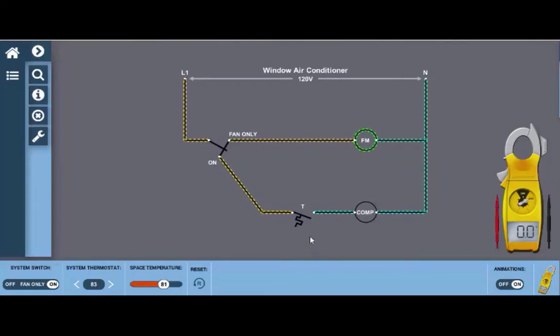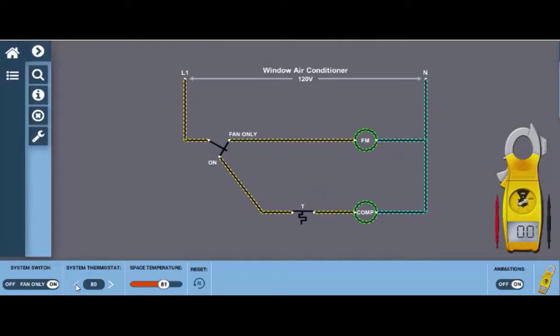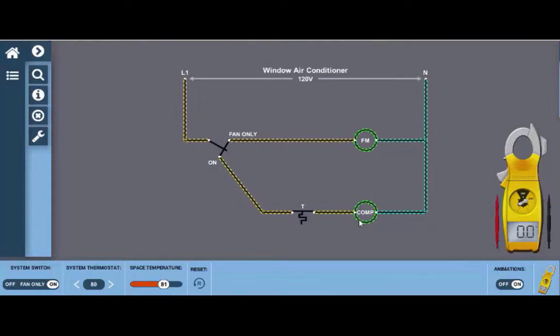But that can be adjusted simply by doing one of two things. You can set the system thermostat here by clicking the down arrow and setting the temperature below the space temperature set point which is currently at 81 degrees. And we see when this happens that the thermostat closes and our compressor lights up indicating that it's energized.